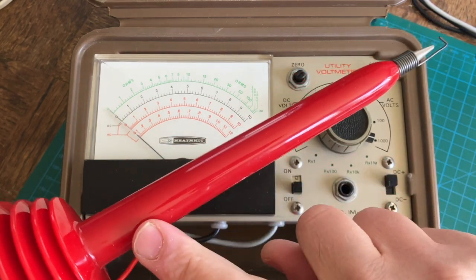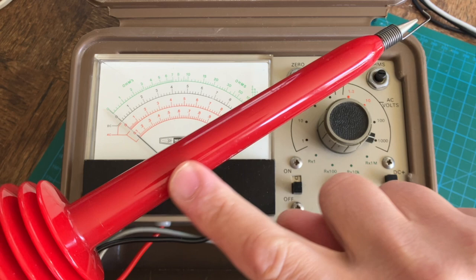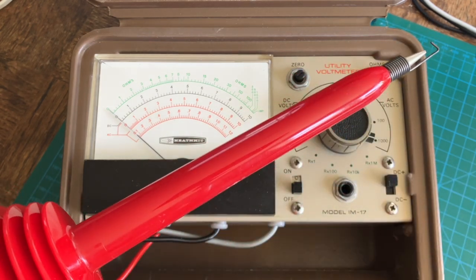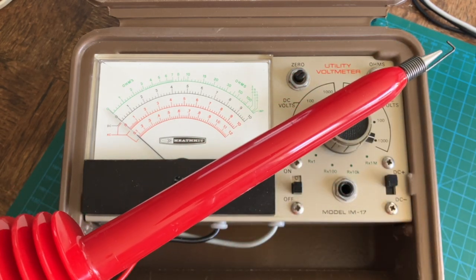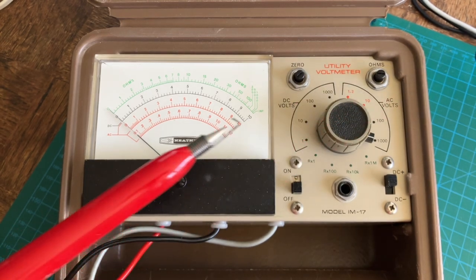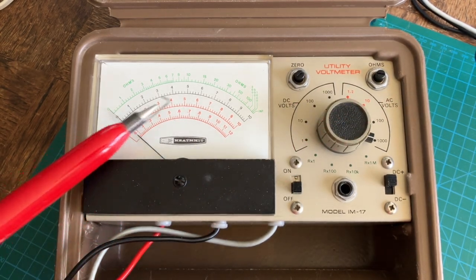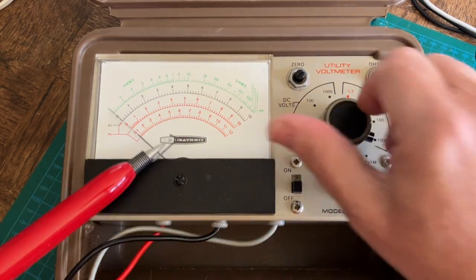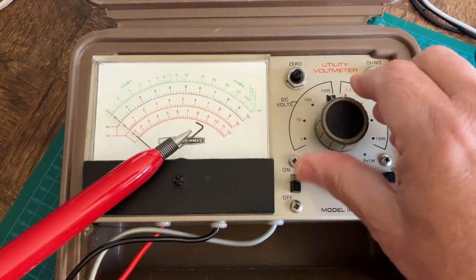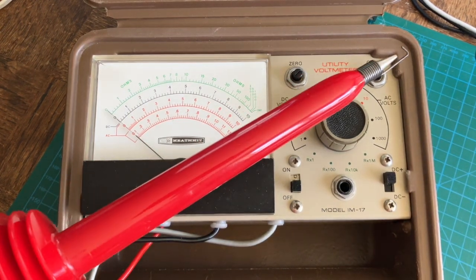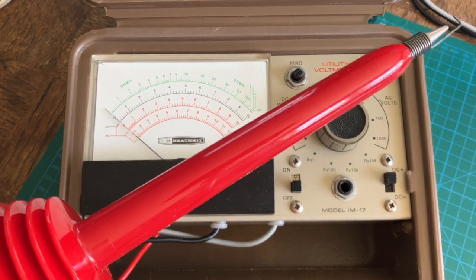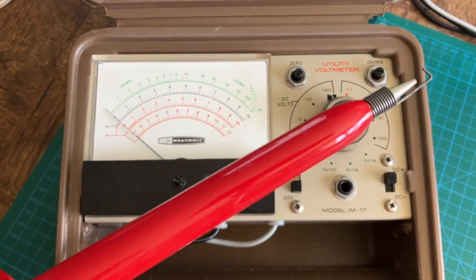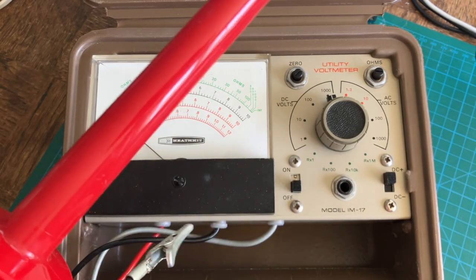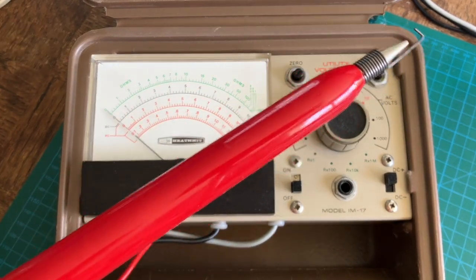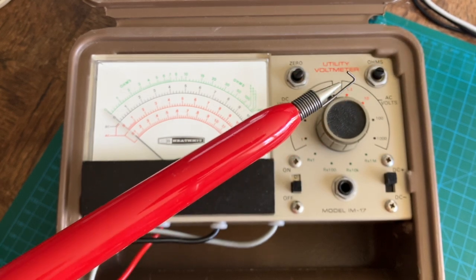This features a 1.09 gigohm giant resistor in here. And so that, with the 11 megohm input resistance, would give you an accurate reading on your DC scale only, and this could basically be thought of as a times 100 probe. So whatever voltage you applied to the tip, with respect to its little ground clip, would be divided by 100 and then fed to the meter.